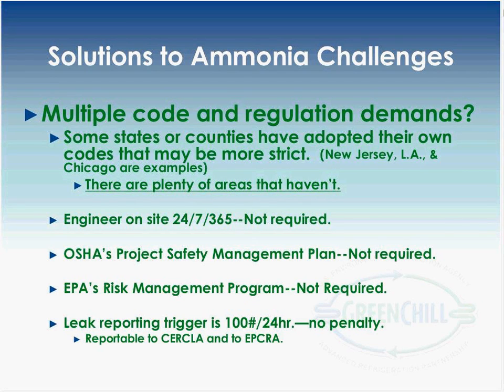OSHA's Process Safety Management plan and the EPA's Risk Management Plan are required for systems with more than 10,000 pounds of ammonia. And I should mention, a supermarket-sized system would have probably 200 pounds or less. So, again, another misconception there. I want to note that there is a leak reporting trigger. If you leak 100 pounds of refrigerant or more within a 24-hour period, you'll report that to CERCLA and EPCRA. And I know what those are. CERCLA is the Comprehensive Environmental Response, Compensation, and Liability Act, and EPCRA is the Emergency Planning and Community Right-to-Know Act.